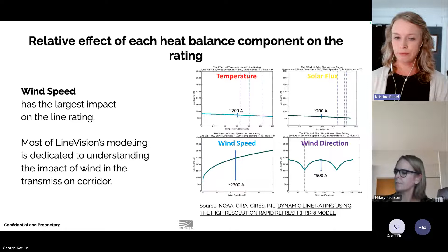You can see, for instance, with ambient temperature and solar flux, the impact is relatively small. That doesn't mean it's not meaningful. Hilary will be talking probably a bit about FERC 881 as well, which requires ambient adjusted ratings on transmission lines. And the impact of factoring in ambient temperature for your calculation can still give you a few percent increase, maybe up to 10%. But really the big benefit of dynamic line ratings comes in due to the wind speed. You can see that we're more than 10xing that impact as we go across the range of wind speeds used on this chart. So it really illustrates that wind is the most impactful variable in this heat balance equation. Next slide, please.